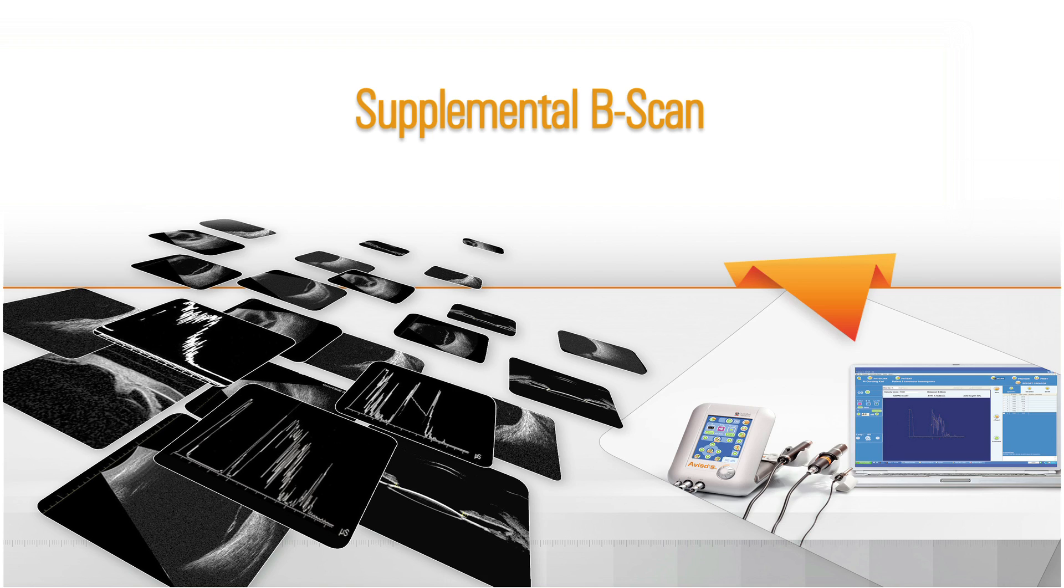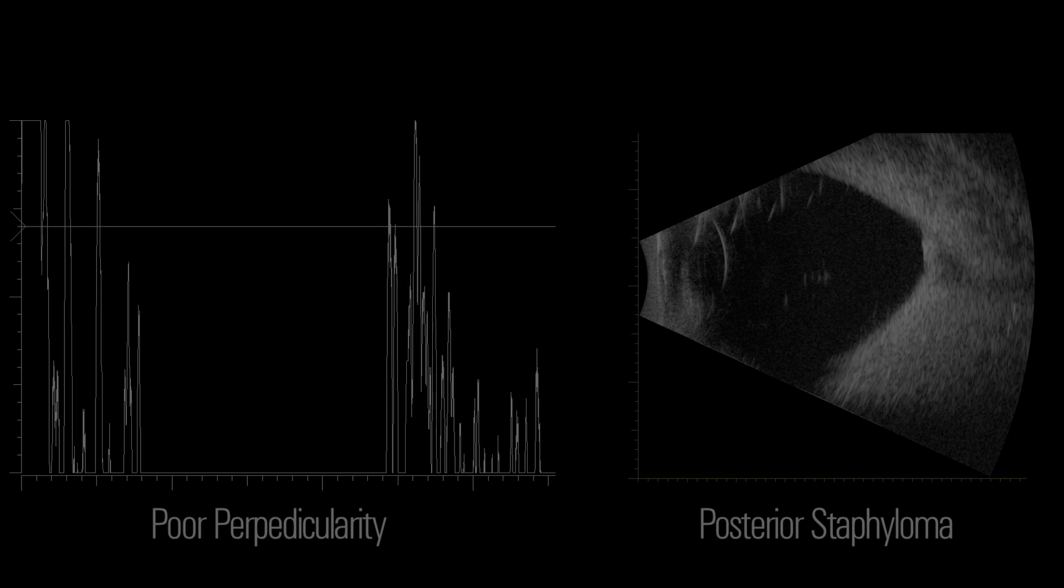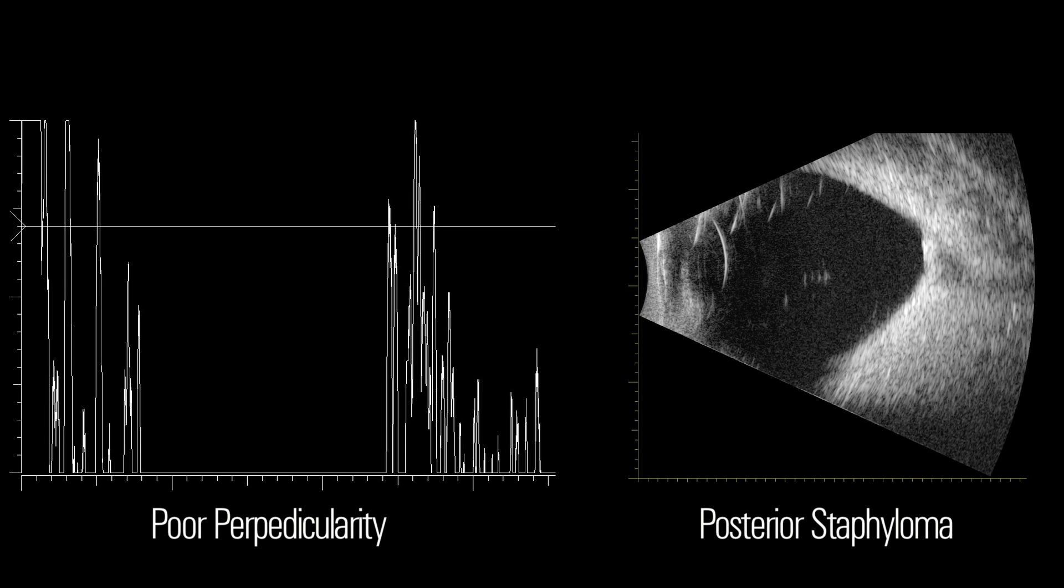Supplemental B-Scan. Under some circumstances, one-dimensional A-scan biometry should be followed by a two-dimensional B-scan. If achieving perpendicularity to the eye structures is difficult, or if an unusual spike is present and does not disappear with repeat scans and adjustment of the probe's position, performing a B-scan is strongly suggested to rule out the presence of an abnormality that may be causing the difficulty.